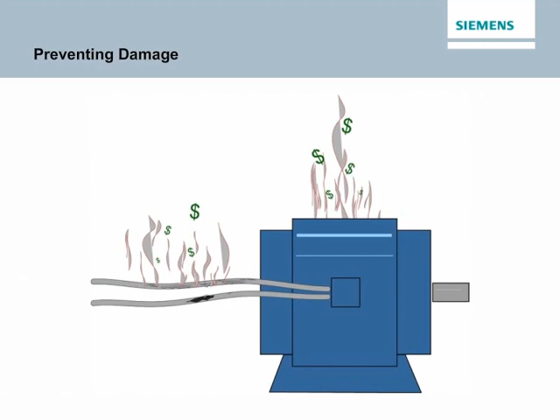The peak short circuit current of the first cycle is the greatest and is referred to as the peak let-through current. The electromagnetic force associated with this current can cause mechanical damage to electrical components. The maximum destructive energy let-through is a measure of the energy associated with this current. It is capable of producing enough heat to melt conductors. A properly applied overcurrent protection device will open the circuit quickly, limiting peak let-through current, IP, and energy.